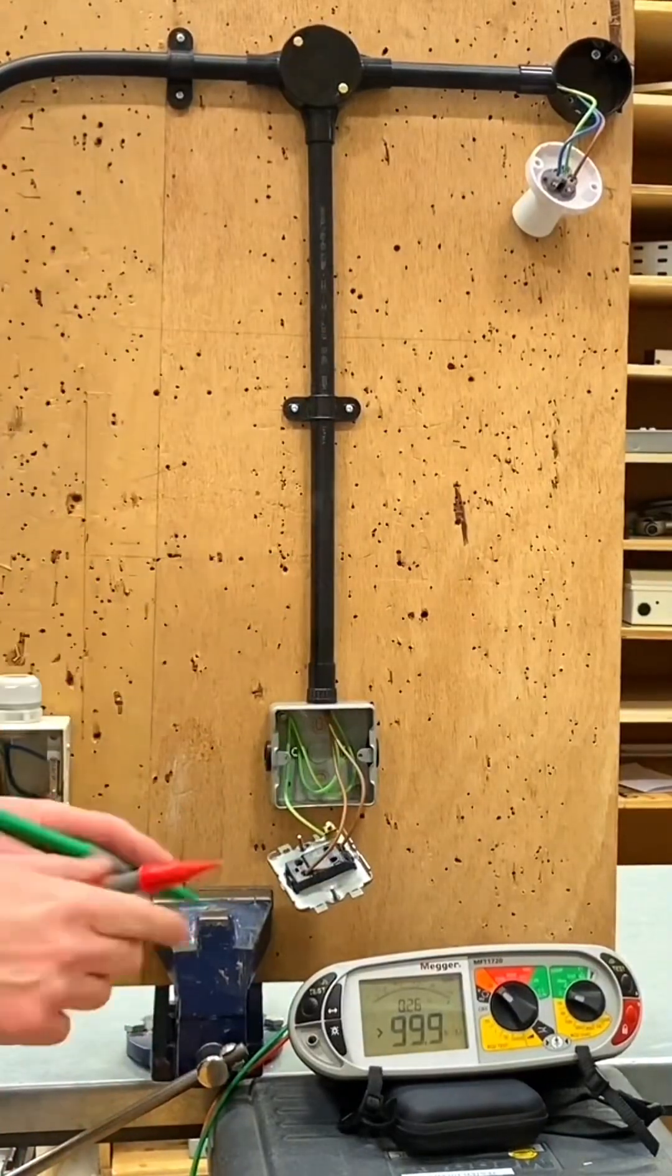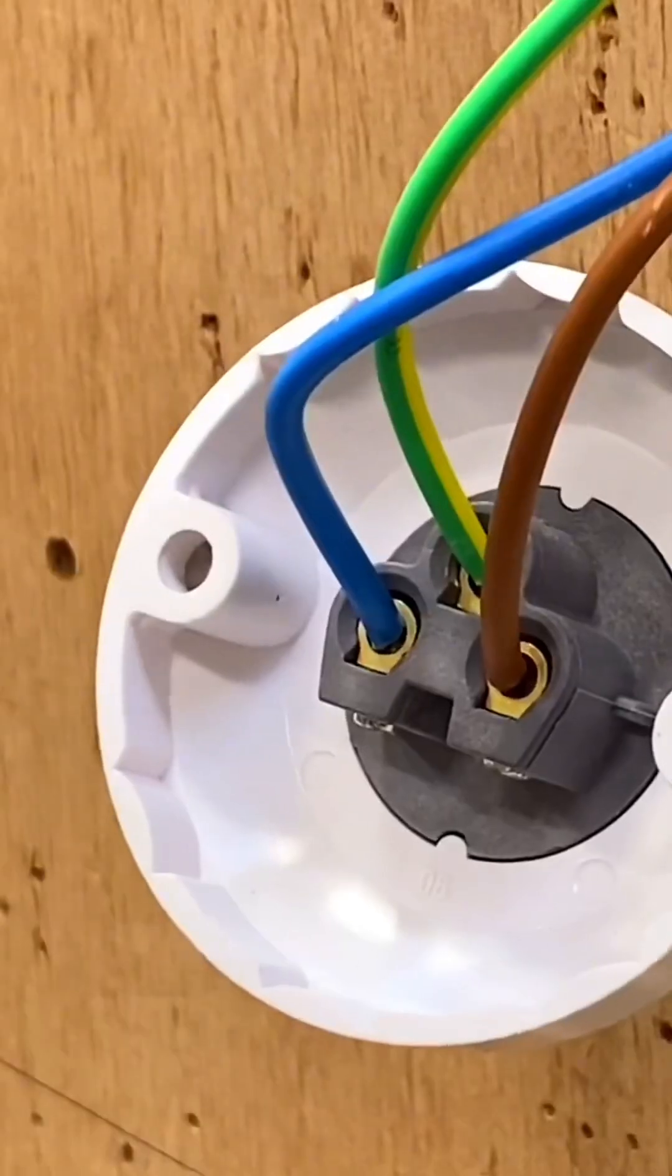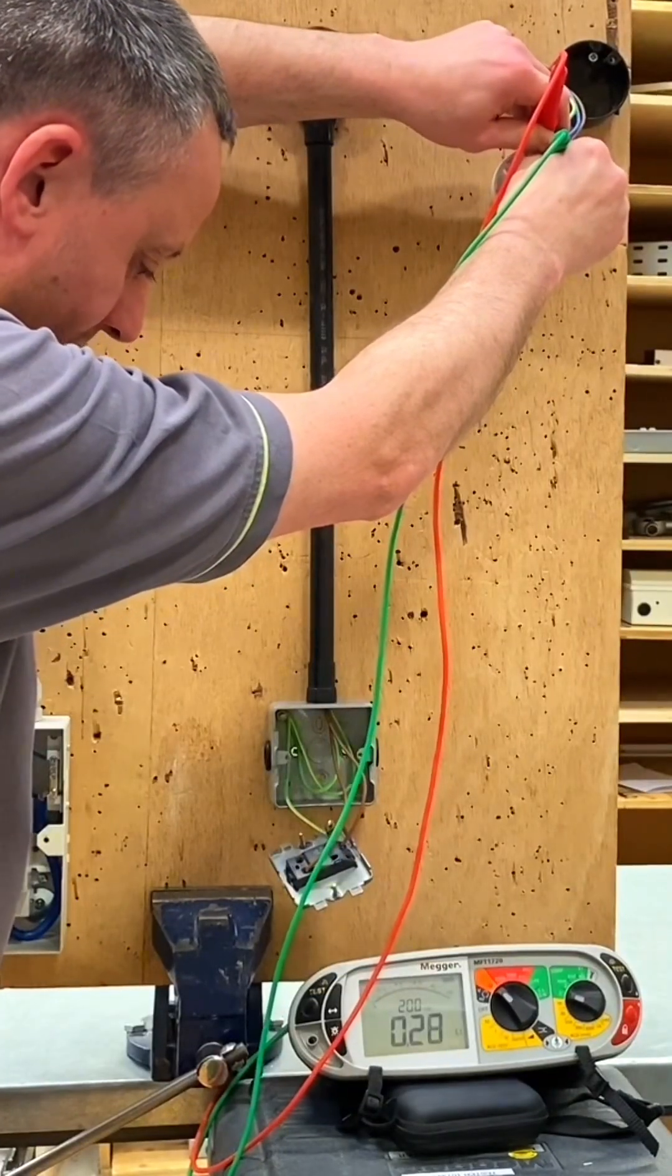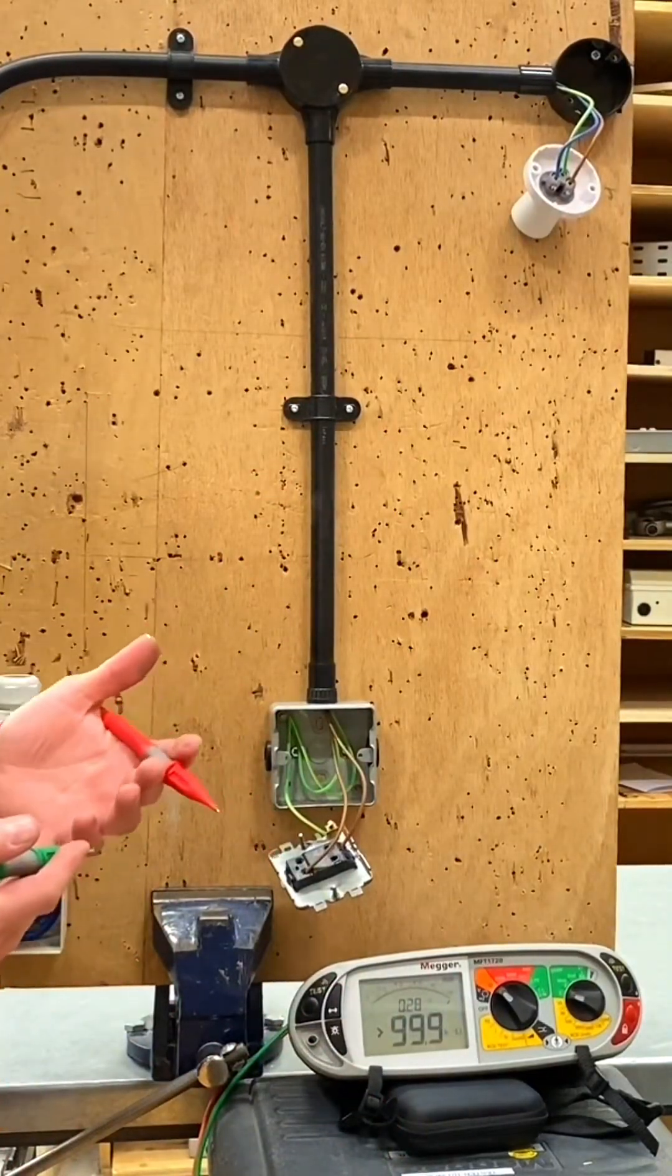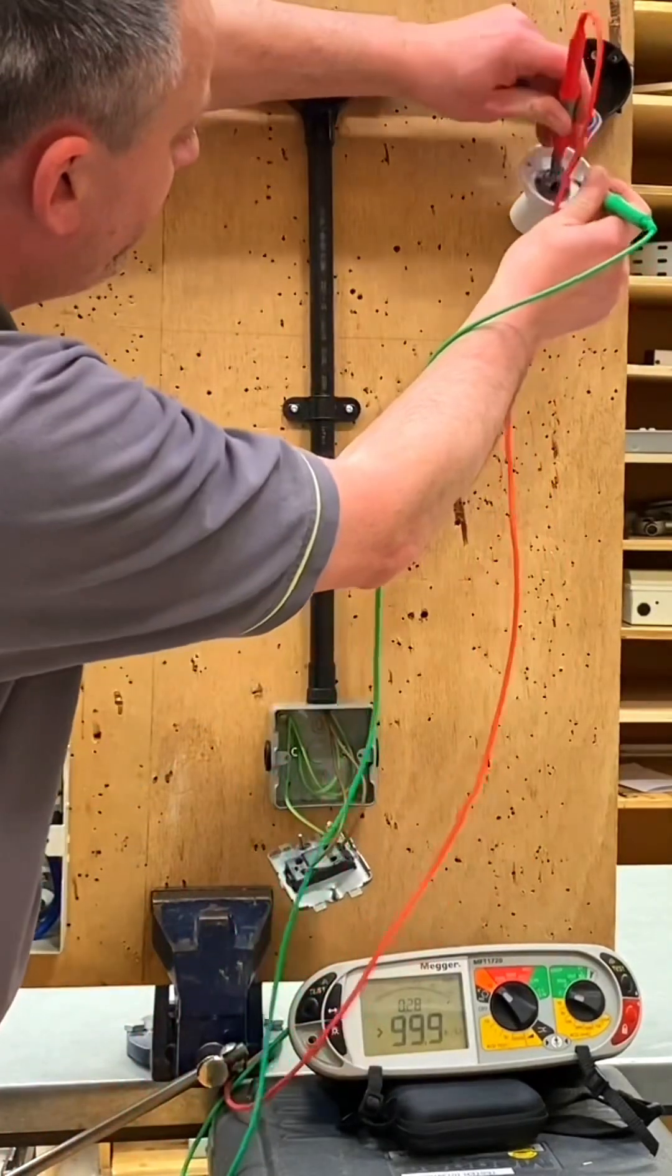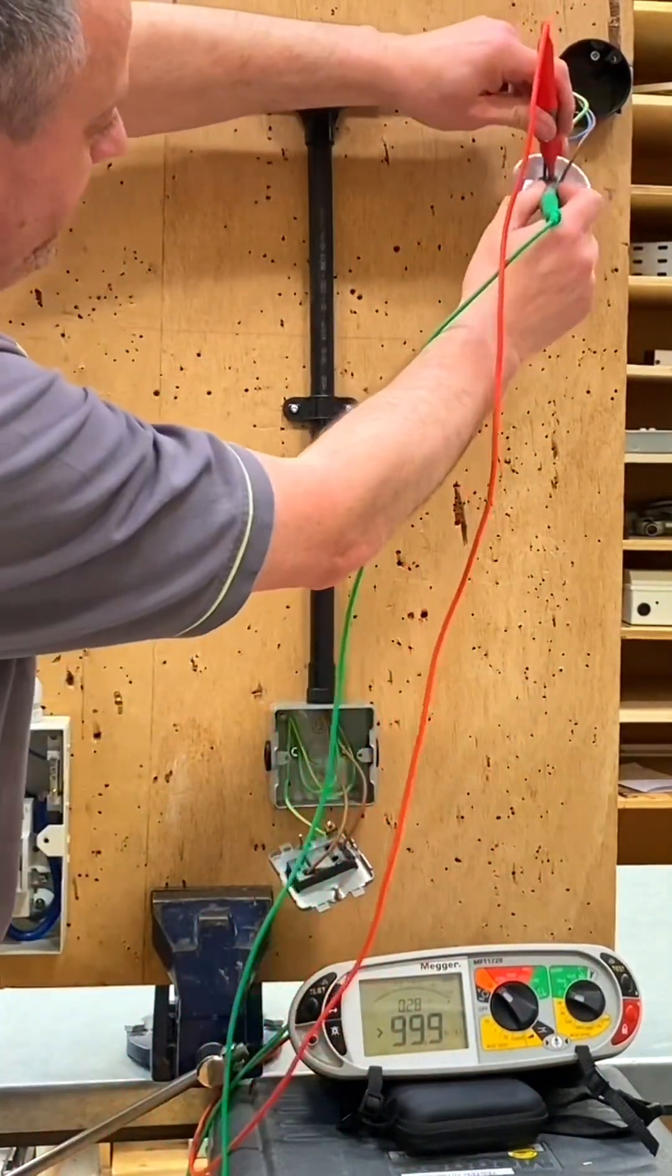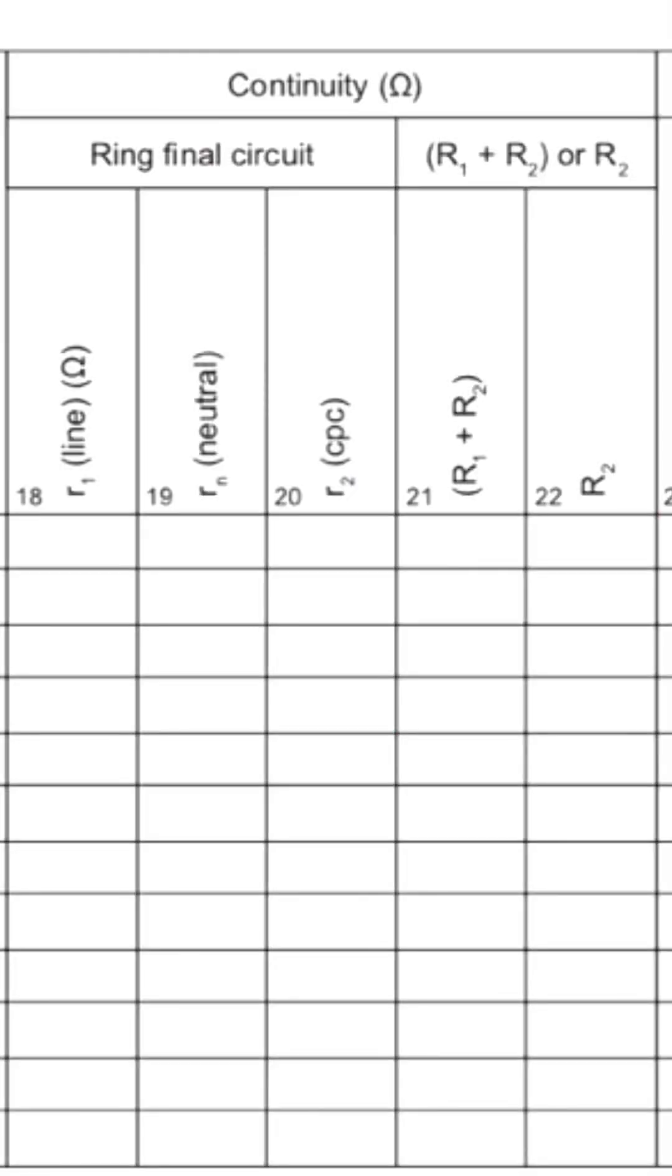Let's operate the switch, go back up again, onto the CPC and then onto the line itself, and we have a reading of 0.27. So we had no reading to start with, operate the switch, we have a reading. If we repeat the process and operate the switch again, we should now find we have no reading, and we don't. Repeat the process again, operate the switch back onto the line and CPC up here, and we should find we got a reading.